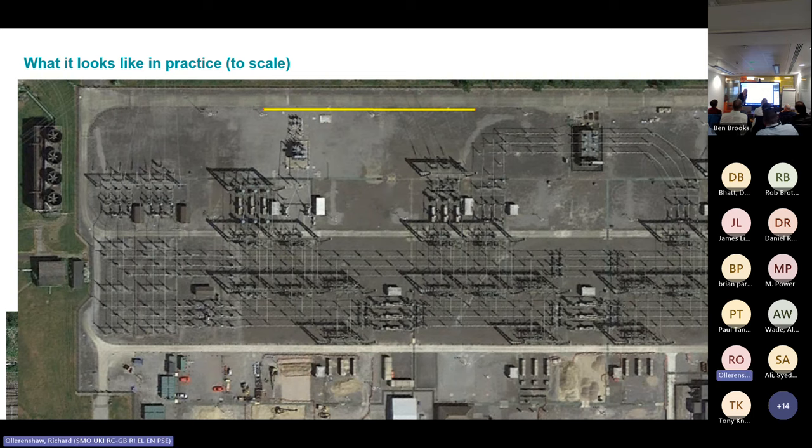Well, let's do a bit of a comparison, first of all. This is the smallest conventional feeder station I could find. It's a beautiful example of British rail engineering, absolutely built down to the penny. The Scottish Power compound, which doesn't even have a circuit breaker in it, is literally just a wooden pole route fed onto a transformer, fed directly onto the railway switchgear. Absolutely beautiful design. And you would have every 15 to 20 kilometres a sectioning substation to allow your protection to work effectively and share current between lines.